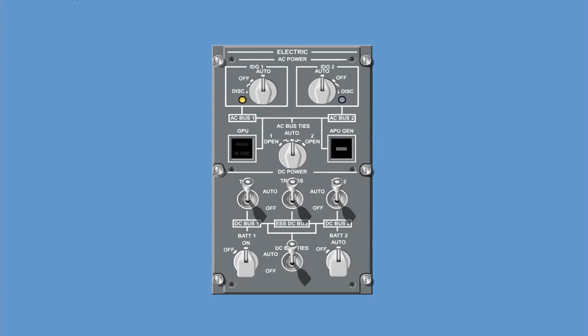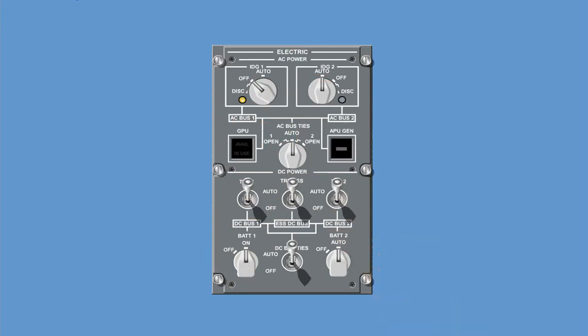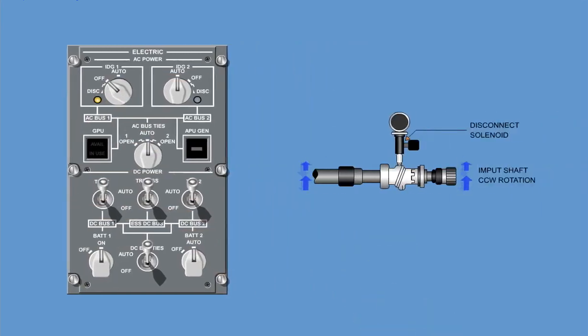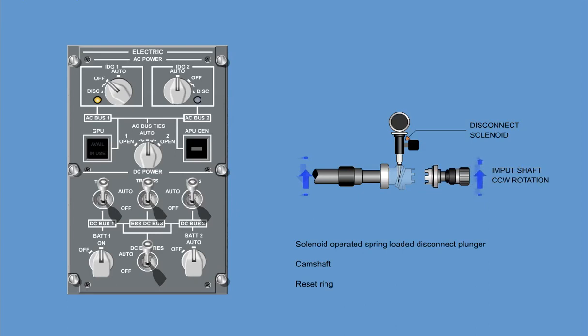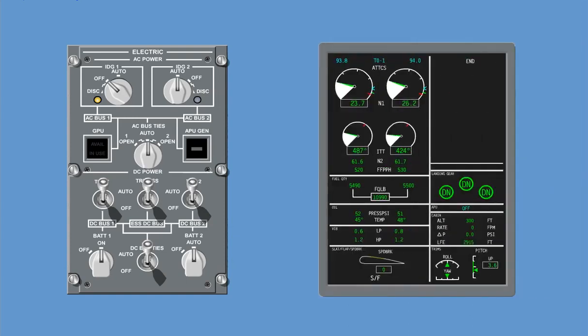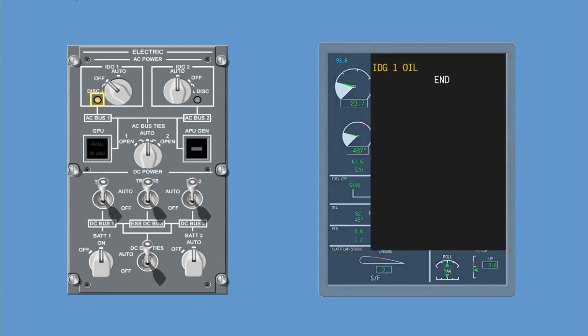In case of malfunction, the IDG can be manually disconnected through a switch located on the cockpit control panel, controlling the electric-mechanical disconnect mechanism, which is part of the IDG input shaft. This mechanism consists of a solenoid-operated, spring-loaded disconnect plunger, camshaft, and reset ring. The manual disconnect should be performed if the associated cockpit IDG disc amber indicator light and/or the IDG oil CAS message is displayed. These indicate low oil pressure or high oil temperature in the IDG.